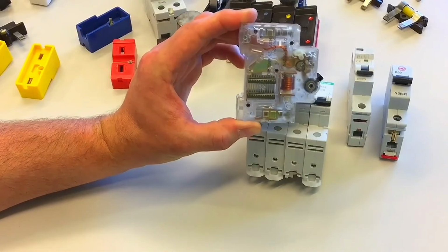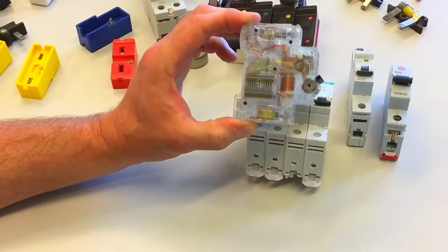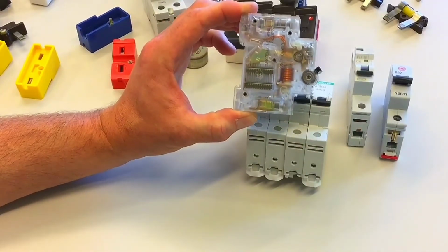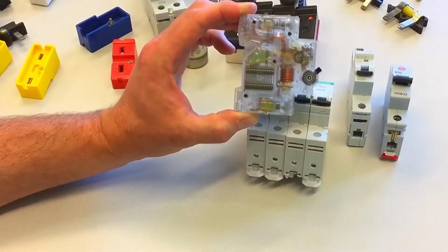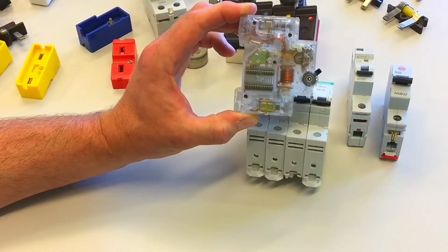a circuit breaker. When you overload this circuit breaker, in other words, ask it to carry more current than it's designed to do so, it's rated for this one at 20 amps. Fusing factor would be 1.5 times that, so roughly 30 amps. But we're looking at the bimetal strip at the top here. When we ask it to carry more than its 20 amps, it starts to get warm. That bimetal strip eventually, over time, will cause the disconnection of the circuit.